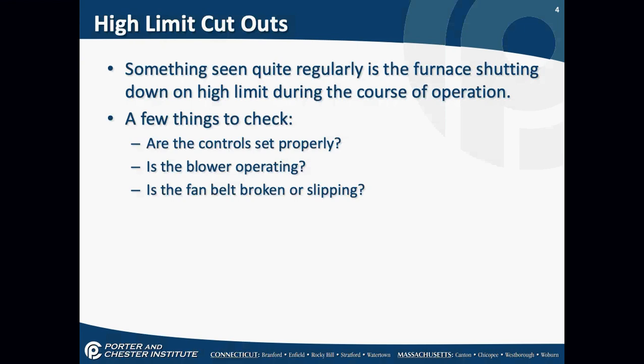Well, think about the air side. Am I moving air through a heat exchanger that's absorbing the heat? Sure. Well, I would hope so, since I'm putting heat into the house. So I have air being pulled through the blower motor. That air is going across the heat exchanger, absorbing heat from the combustion side of it, and blowing out the registers into the house. Okay, that's what keeps the heat exchanger cool and under the high limit.